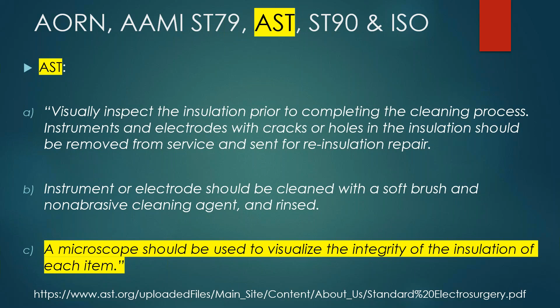It goes on to say the insulation scanner should be used to detect the release of stray electrical energy along the length of the insulation, and then it goes on to say securely packaged for sterilization. So it actually goes into packaging when you put it back into the tray or set, to minimize movement that would cause more damage to those devices even after you tested them. AAMI ANSI ST90 goes into your performance qualification, your PQ, and says you need to visually inspect for defects.